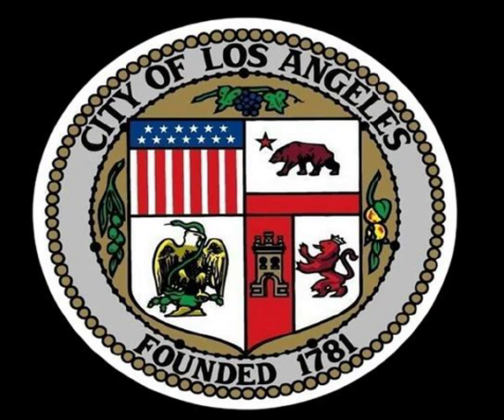We go down to 1442 with the loss of this transmission. Ultimately, after we put on some generation, a total of a little over 1,800 megawatts online, we were able to cover our load. Our net capacity equals our total load. At the end of this event, we had about 135 megawatts of in-basin generation we still could have utilized to cover load. But if load had been greater than that 135, we would have had to shed customer load.